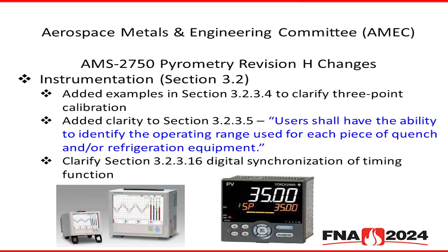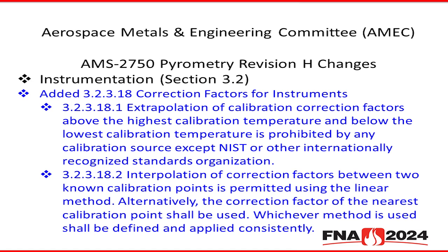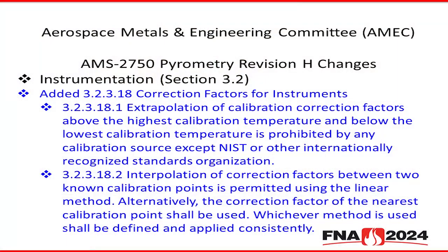We also added a little clarity to the specification on the digital synchronization of timing functions. We also talked about extrapolation. We've always talked about extrapolation when it came to thermocouples, but we also finally added it in for instrumentation as well. With the specification, that extrapolation is never allowed. We did have to put back in, way back in, I think it was Rev E, when we did some work with NIST, that our national standards actually extrapolate data above, I think it's 2200 degrees. So all those thermocouples you're using above that are calibrated, it's been extrapolated by our national standards. So we can't do it, they can. We also talked about interpolation of correction factors between two known points, as long as you're using the linear method. So again, more clarity, more understanding of the specification.